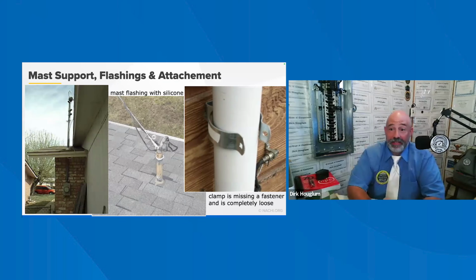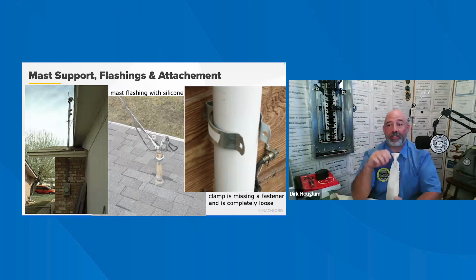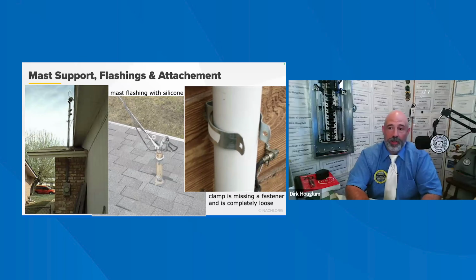A mast in excess of 3 feet above the roof surface may require support. The weight of the cable assembly is considerable, and when that applies to overall tall masts, it has the ability to bend right over. For that same reason, the inspector should report anything other than the cable assembly being supported by the service mast. The inspection on the left image shows tall masts that lack adequate support. It is common to see telephone cables, TV cables, satellite dishes, clotheslines, things like that, supply to the remote building being supported by that same mast.